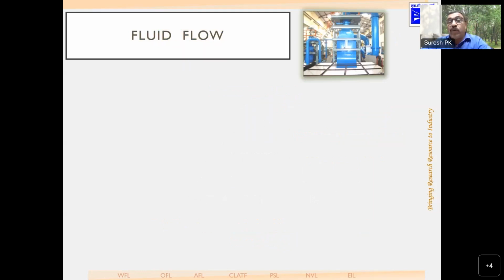So now I will come to fluid flow. The concept earlier used to be that when you put a meter and make a measurement, it is correct. That is not true. The fluid flow is affected by the fluid. As Dixit Sahib has rightly pointed out, it is affected by the fluid, it is affected by the flow, and it is affected by the flow meter. The fluid can be two-phase or single-phase, it can vary with temperature, and it can vary with pressure. The pressure may be varying. There are so many factors involved in the fluid. That is the complication of fluid flow measurement.